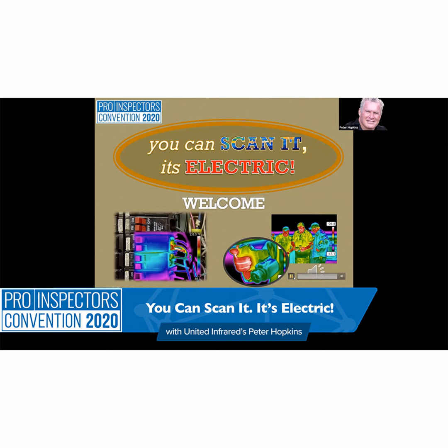This is an example where this client required us to be suited up. Just so you know, some of the rules that have changed in thermography is that if you're beyond the arc flash zone, which is typically about 6 feet back, you don't have to have any of this gear on. The gear is required for the electrician who is opening and closing it. The risk is on this equipment when they open it, not necessarily when it's open like that and I can go over there and look at it.